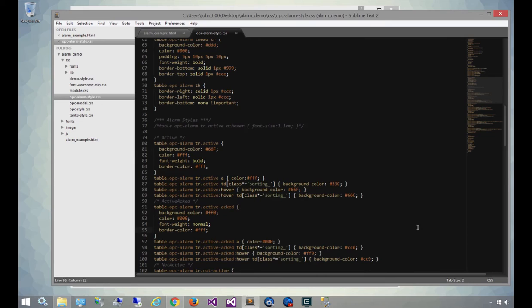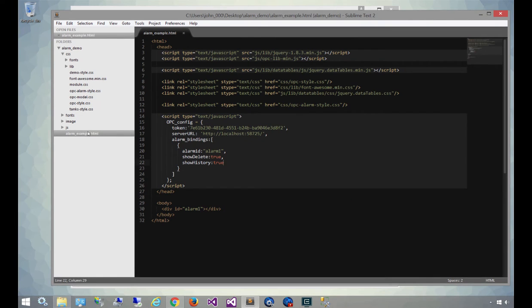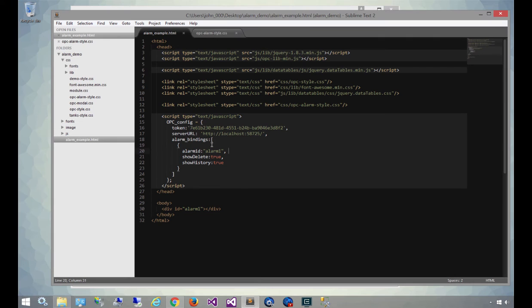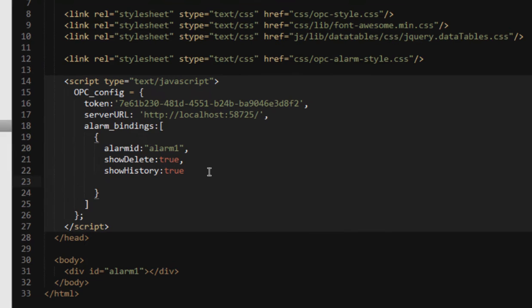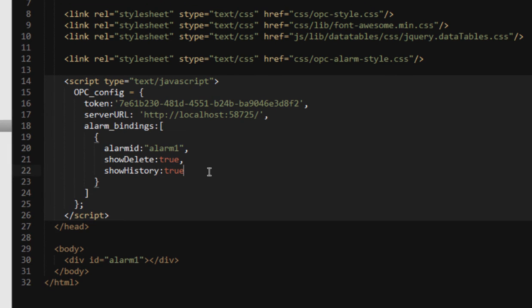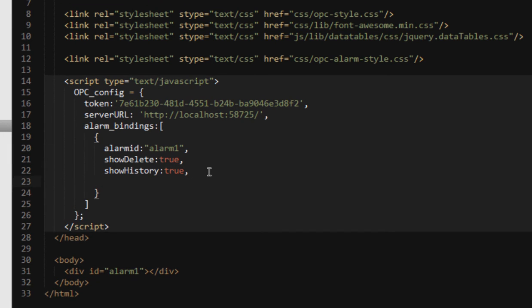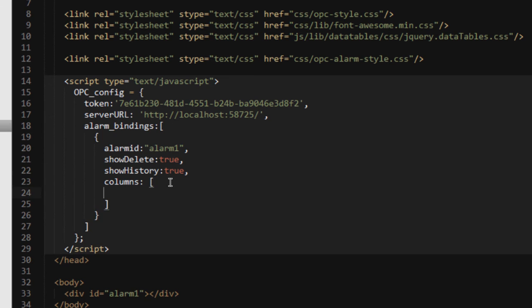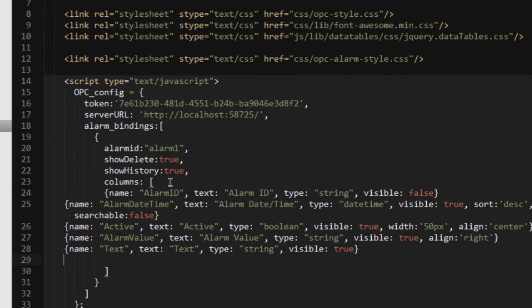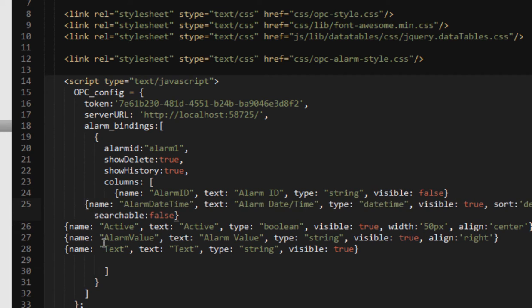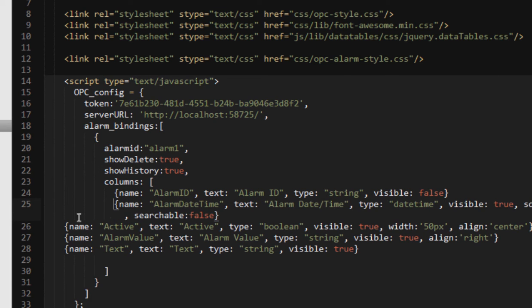And you can modify these styles for each type of alarm that you've got based on its status. Also by default, the alarm control displays all of the available columns. You can choose which columns you want by including in the OPC config alarm binding a columns array. Once you do this, you're taking over the display of the alarm control. So you'll need to include all the columns, including the alarm ID, and all of the attributes on each one.